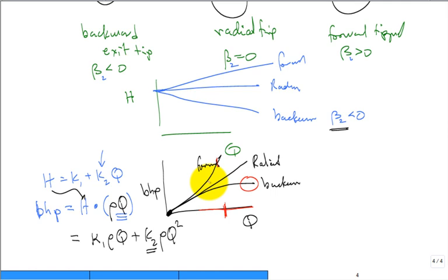But what's the benefit of it? The forward face is going to give you a higher H, isn't it? Isn't this a higher head? So it's going to boost that head. In an air system, when you have a blower motor, it's not that big of a deal. And so it's curved forward, and you just want that flow. It pretty much gives you a decent flow with a pretty good head. Okay, I'm doing a pretty poor job of explaining why water pumps have impellers that are backward face. Really cheap pumps are just straight out radial. Some that really need to deliver super high head will be curved forward, but they're a little risky for water, but they're okay for the air.